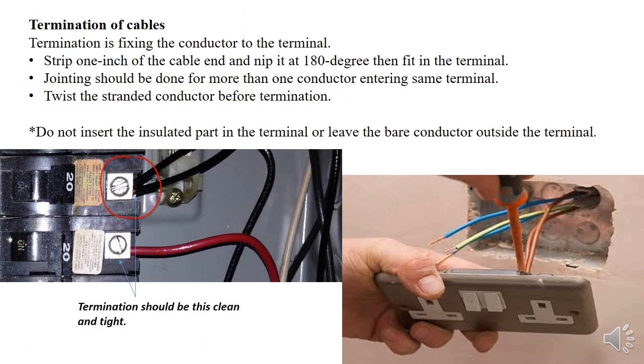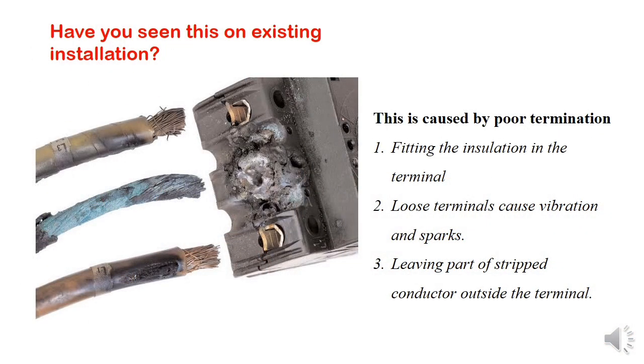For termination, ensure that the bare stripped part of the conductor is not visible hanging on the surface, and that the conductor insulation is not going inside the terminal. Poor termination causes problems — a conductor not well stripped, or a conductor stripped excessively, are common challenges. Ensure you cut only the piece that fits the terminal, avoid loose terminals, and ensure no bare part is left exposed or insulation inserted inside the terminal.